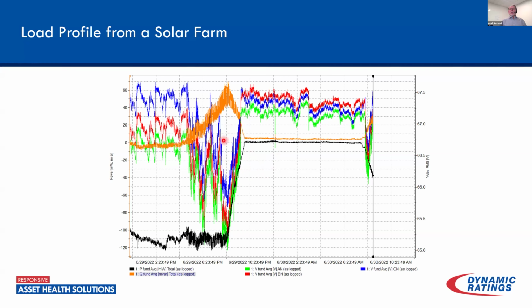But again, the fast ramping of these renewable assets can create some havoc when it comes to the insulation in our transformers. And it can also impact our switchgear and stuff like that. In this case, it's not uncommon. For solar farms and wind farms, you could have fast megawatt ramps of up to 50 megawatts per minute. So they could be coming on very, very quickly, and that's going to stress our insulation.